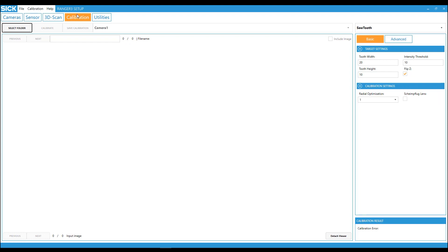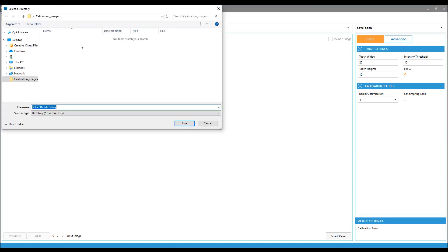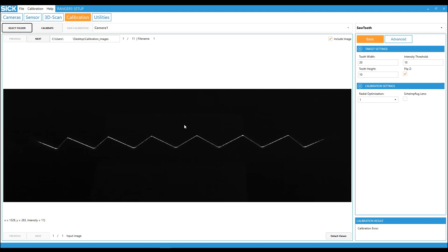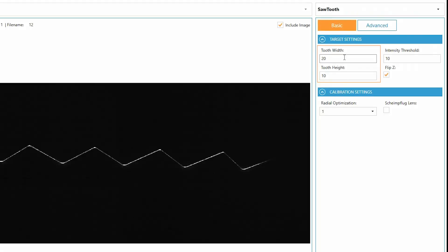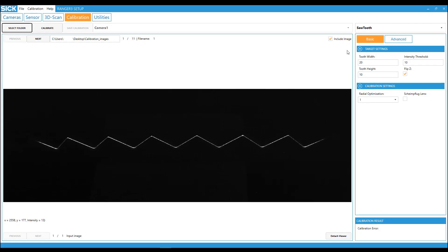To run the calibration, select the image folder. Set the tooth width and height, which is indicated on the sawtooth target. In our case, it would be 20 and 10. Then click on calibrate.